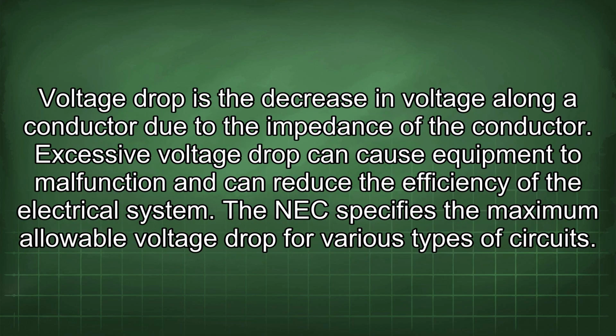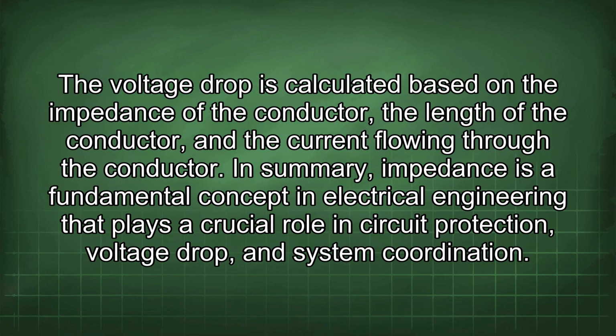Voltage drop is the decrease in voltage along a conductor due to the impedance of the conductor. Excessive voltage drop can cause equipment to malfunction and can reduce the efficiency of the electrical system. The NEC specifies the maximum allowable voltage drop for various types of circuits. The voltage drop is calculated based on the impedance of the conductor, the length of the conductor, and the current flowing through the conductor.